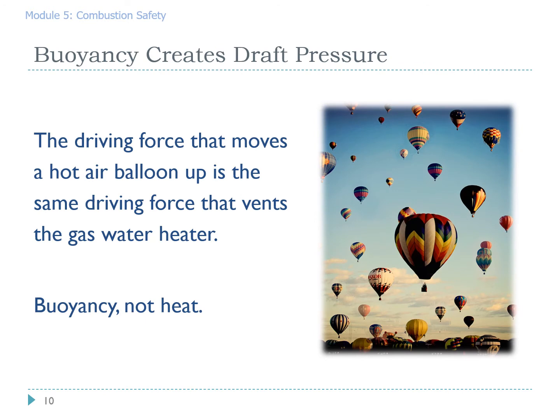Well, we're all taught in second grade science class that heat rises. That's not exactly true. It's buoyancy that creates draft pressure. Why do these hot air balloons go up? Because the gas inside the balloon is less dense than the surrounding atmosphere, and the atmosphere pushes it up. As a thought experiment, what happens if we fill these balloons with 200 degree water? Well, there's lots of heat in there, but it's no longer going to be buoyant. It's going to be heavier than the atmosphere, and the balloons would quickly fall to Earth.